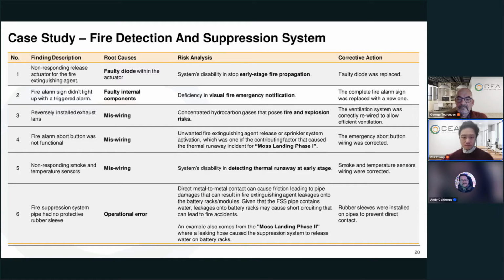The root cause of most of these problems can be traced back either to internal component failure, which is the case for findings number 1 and number 2, where we find a faulty diode within the actuator and internal component failure in the fire alarm sign, or to miswiring or misoperation from the manufacturer for the rest. The associated risk with any fire suppression system failure has to do with the system's deficiency in detecting and stopping thermal runaway events at an early stage.